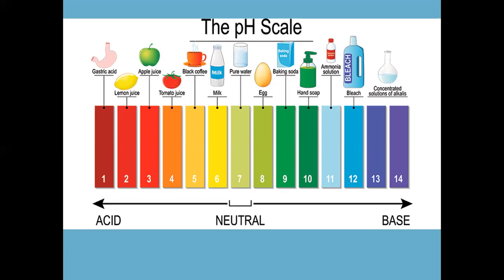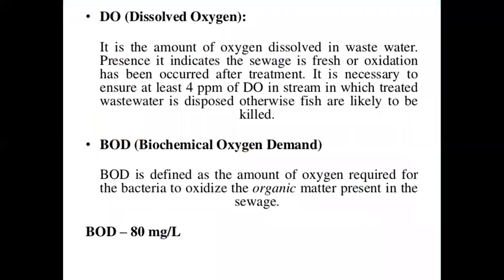The pH scale shows that below 7 is acidic and above 7 up to 14 is alkaline or basic, with 7 being neutral. The acceptable range for treated sewage is 6.5 to 7.5 (neutral). After treatment, if oxidation has occurred, it is necessary to ensure at least 4 ppm of dissolved oxygen.